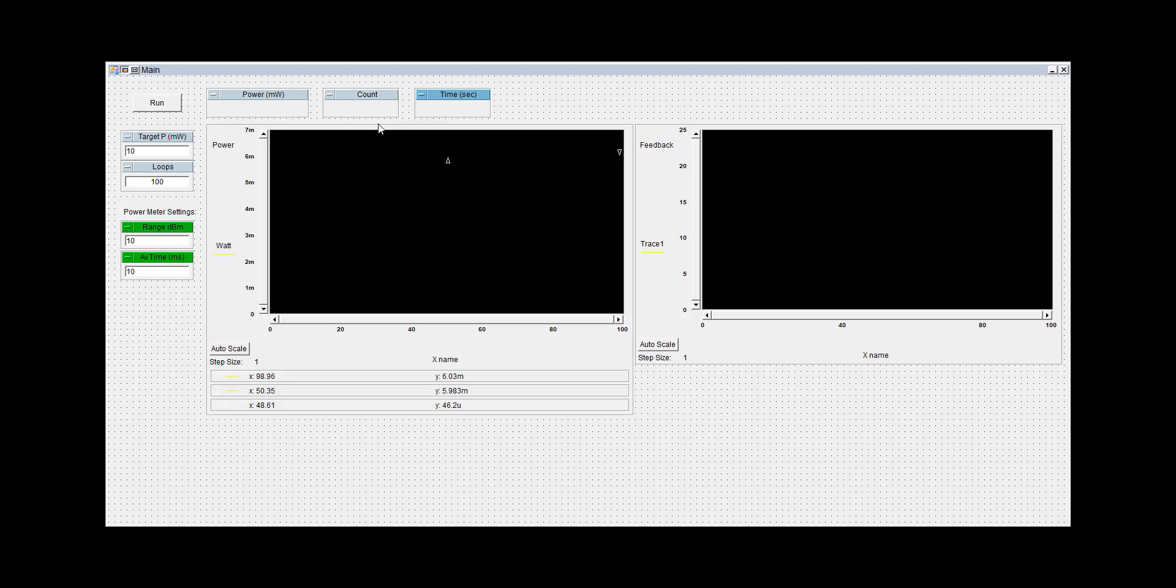when we're completely aligned with the polarizer. We'll set the target value to a little bit higher than that, 10 milliwatts. So the program is, and the N7785C is always trying to go to a higher value.